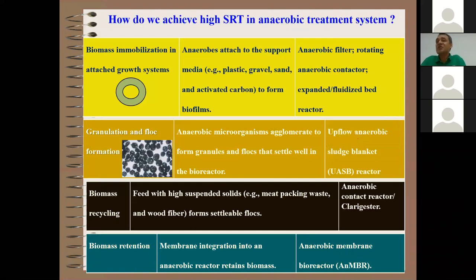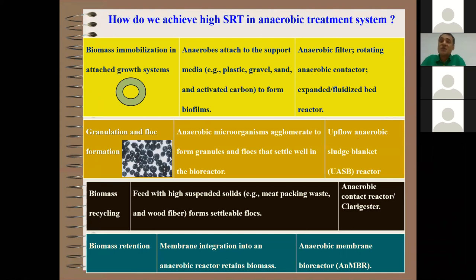The first technique to maintain long SRT is biomass immobilization. We use different types of attached growth media — plastic media, sand, gravel, activated carbon, rubber beads — as biocarriers to allow microbes to grow on surfaces and form biofilms, thereby retaining high biomass concentrations in the reactor regardless of HRT. Examples include anaerobic filters (upflow or downflow), rotating anaerobic contactors, and expanded and fluidized bed reactors.